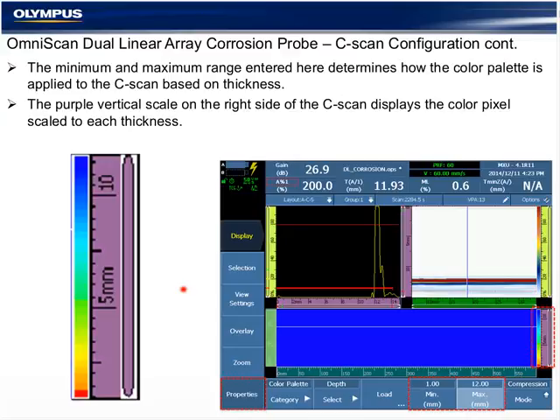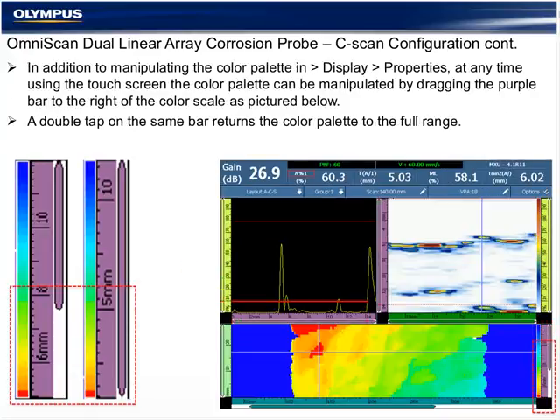After the UT and the gate are configured, the color palette is configured. And again, we have another range here that by default will be the same as our gate thickness range, and a combination of the gate length and start position, the thickness entered under the gate, and the color palette, this will determine the color of our C-scan. Color equals thickness. And it's going to help us in the C-scan analysis to find our low spots quickly.